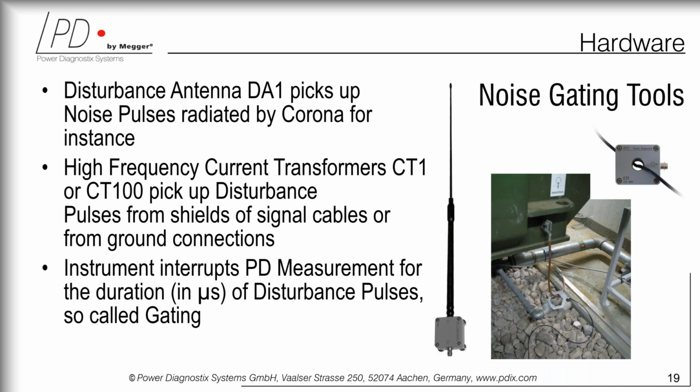I'll be honest, mounting such antennas represents a tricky thing because obviously they will pick up a wide variety of signals. So generally people prefer to have the bushing couplers and also the hatch or oil valves for UHF signal. But this antenna is a noise gating tool and it has its own benefit when employed in conjunction with our devices.